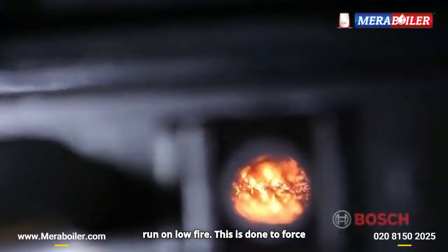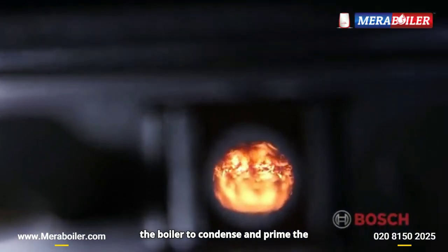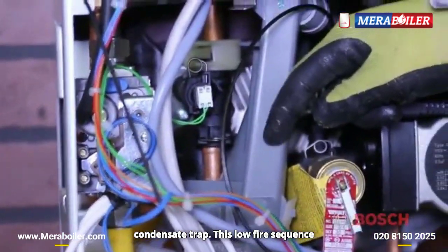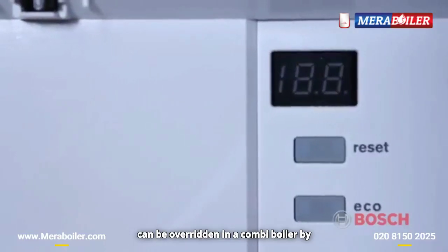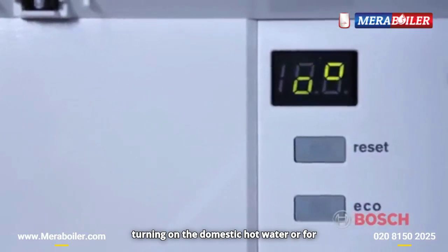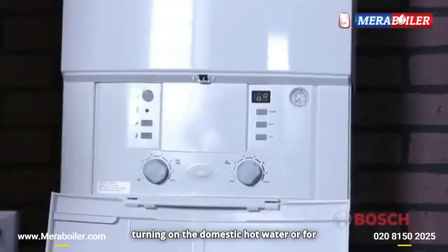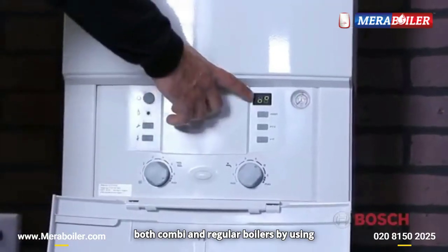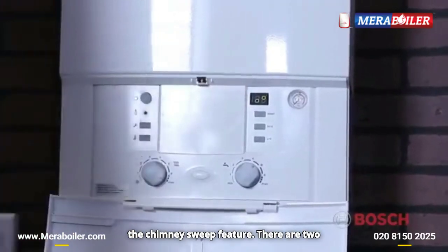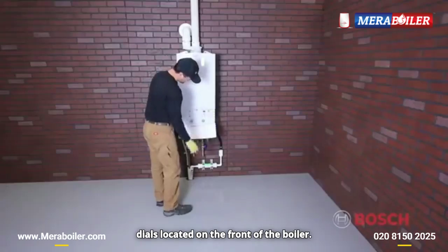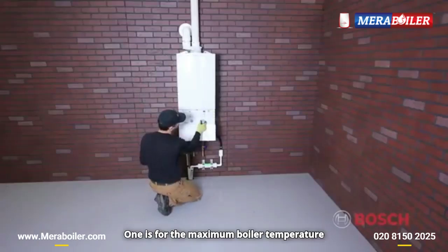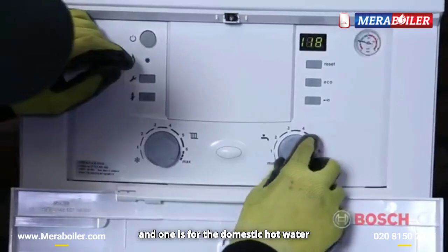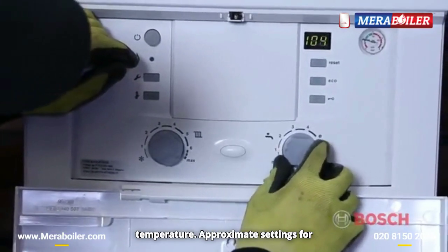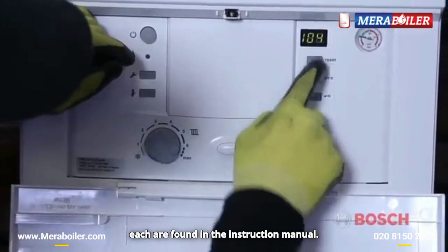For the next 15 minutes, the boiler will run on low fire. This is done to force the boiler to condense and prime the condensate trap. This low fire sequence can be overridden in a combi boiler by turning on the domestic hot water, or for both combi and regular boilers by using the chimney sweep feature. There are 2 dials located on the front of the boiler. One is for the maximum boiler temperature, and one is for the domestic hot water temperature. Approximate settings for each are found in the instruction manual.